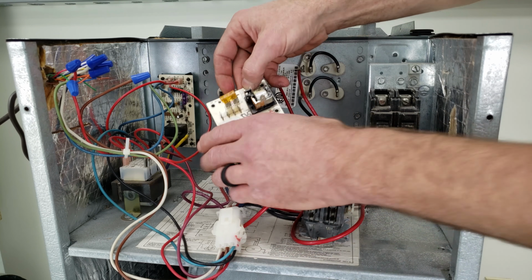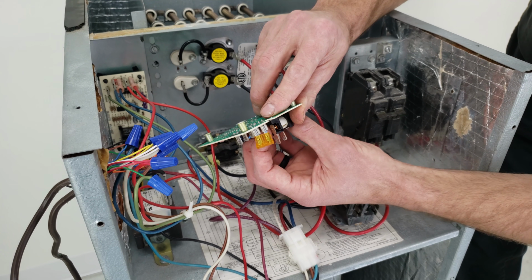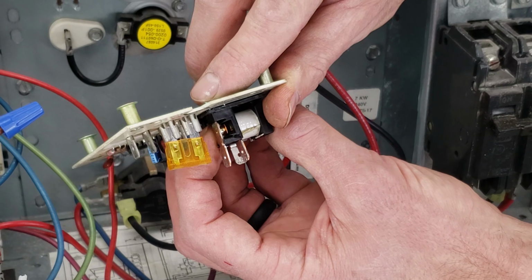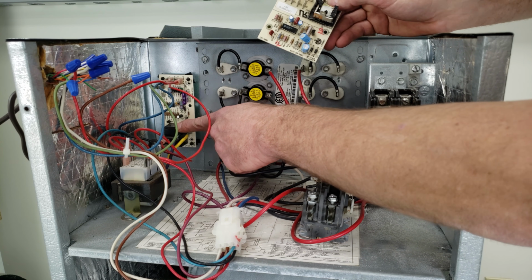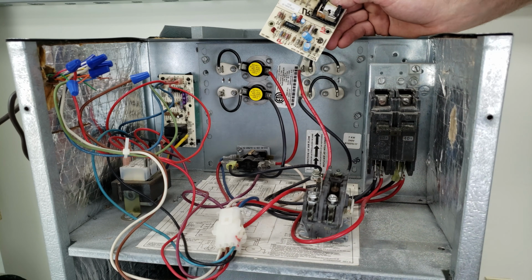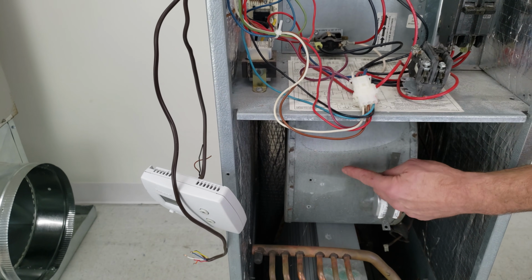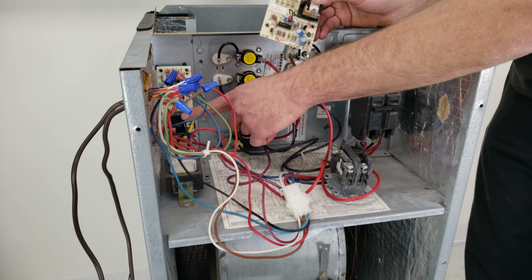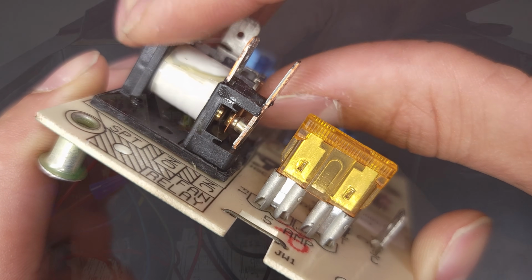So in this case we have a little relay right here, and I don't know if you can see these little contacts. There could be high electrical resistance on these contacts, and that's what's inside this black box. This black box is housing the contacts for the blower motor, and this blower motor is going to be drawing a lot of current anytime that it's running. That current is getting drawn across these contacts. This is one example of one problem that you may have.